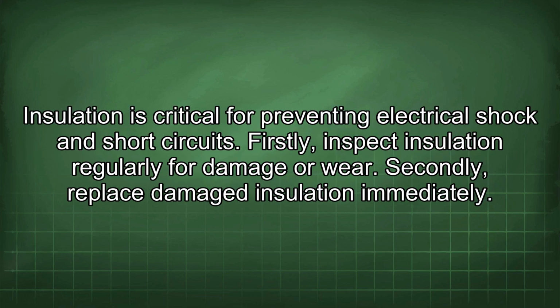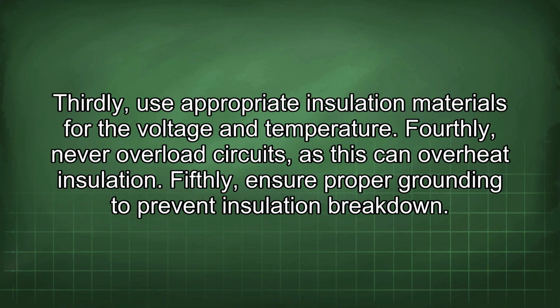Insulation is critical for preventing electrical shock and short circuits. Firstly, inspect insulation regularly for damage or wear. Secondly, replace damaged insulation immediately. Thirdly, use appropriate insulation materials for the voltage and temperature. Fourthly, never overload circuits, as this can overheat insulation. Fifthly, ensure proper grounding to prevent insulation breakdown.